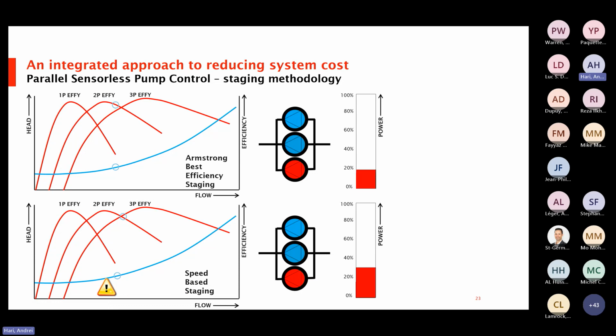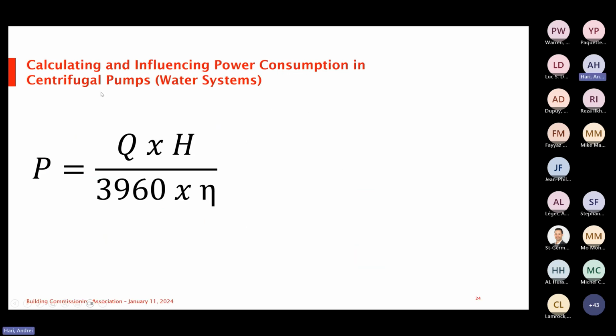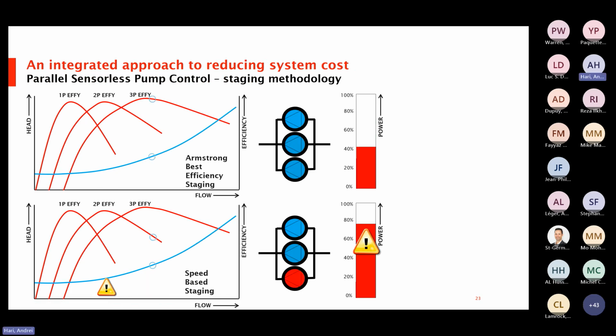The reason this works is simply, if you look at the laws, power is equal to flow times head divided by 3960 times the efficiency. So the end result is that if you're staging your pumps at a higher hydraulic efficiency, you're using less power. It doesn't matter whether you're running 2 pumps here as opposed to 1 pump, because you're at a higher hydraulic efficiency, your overall brake horsepower is significantly less. In this area, you can see up to a 15% power savings. Depending on the number of pumps you're operating in parallel, that power savings can increase to about 20% and up to 34%, depending on the size of the system.